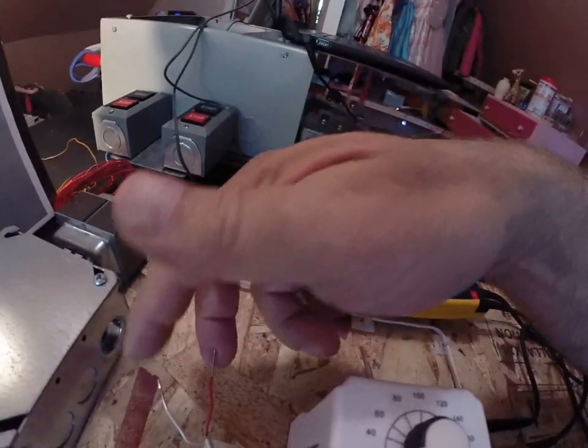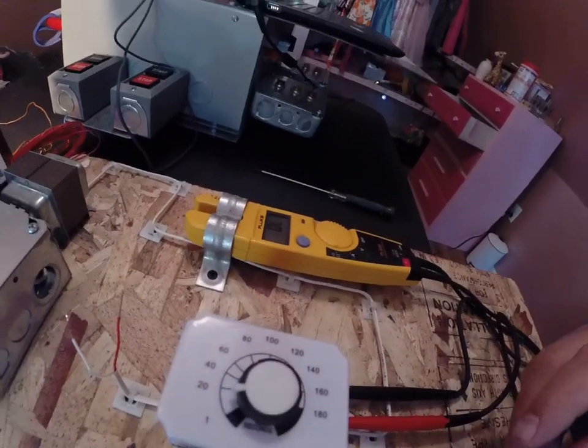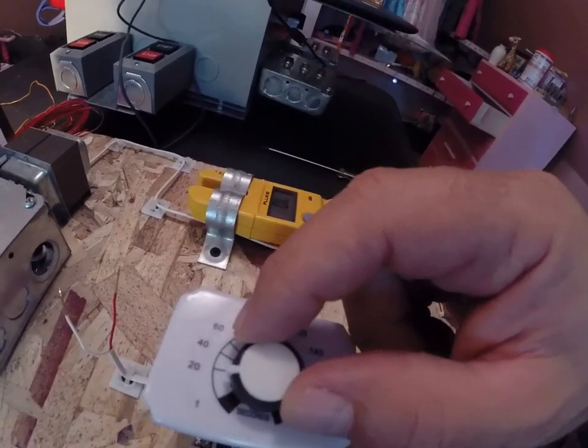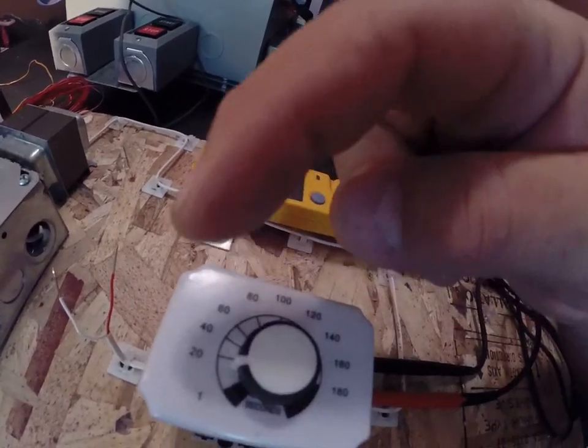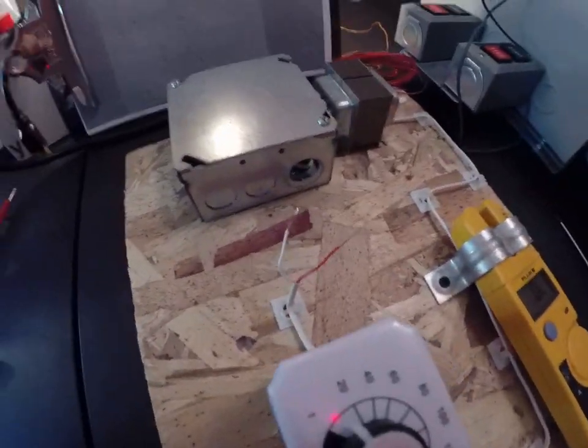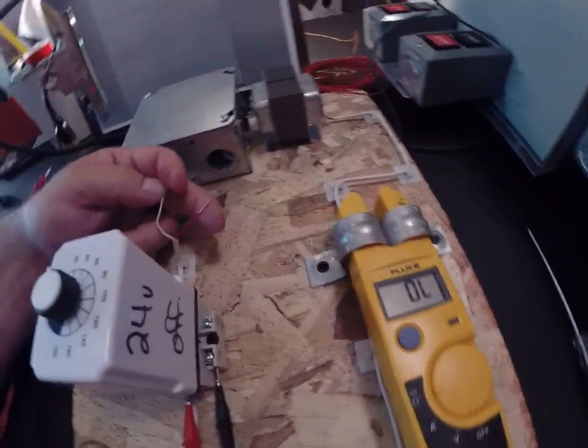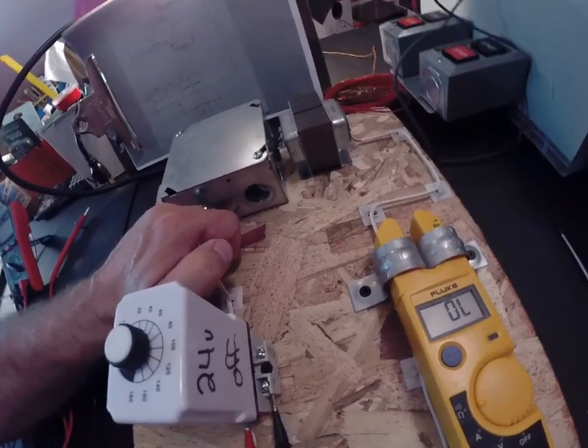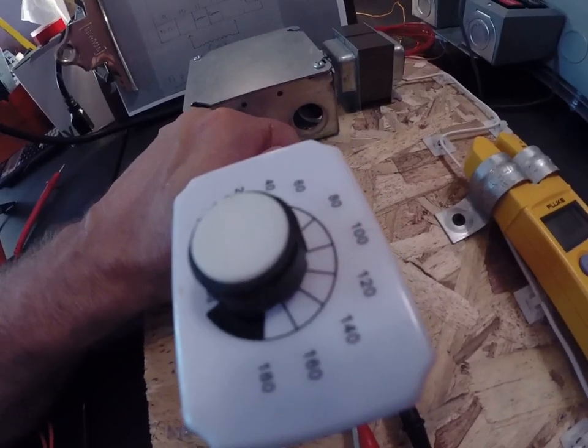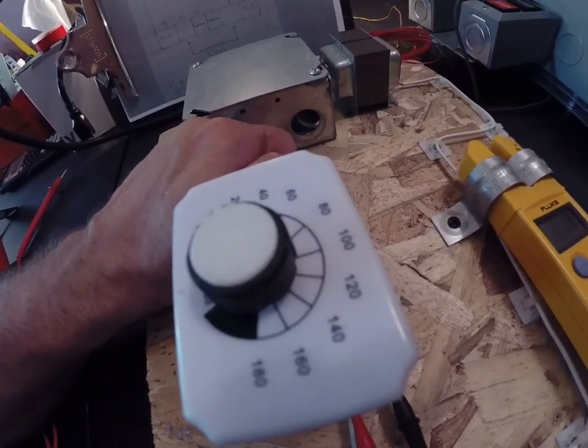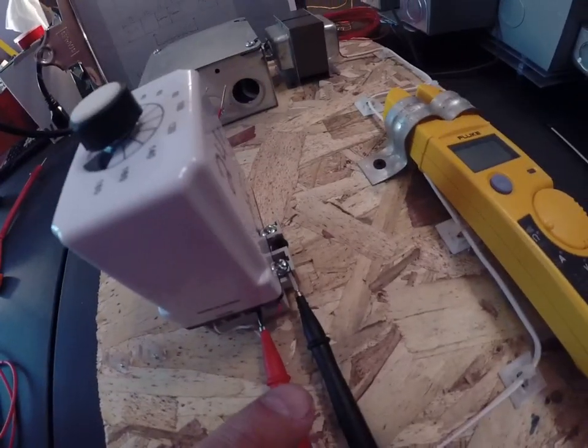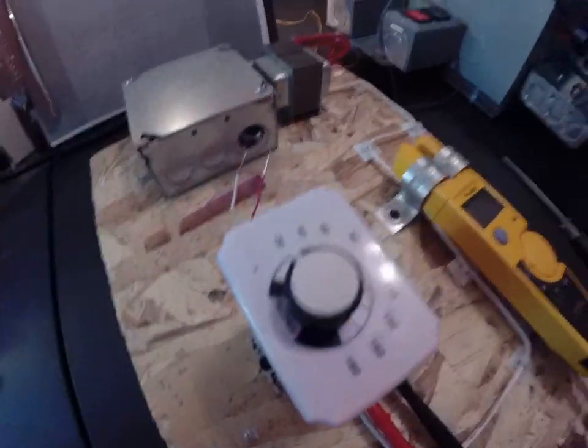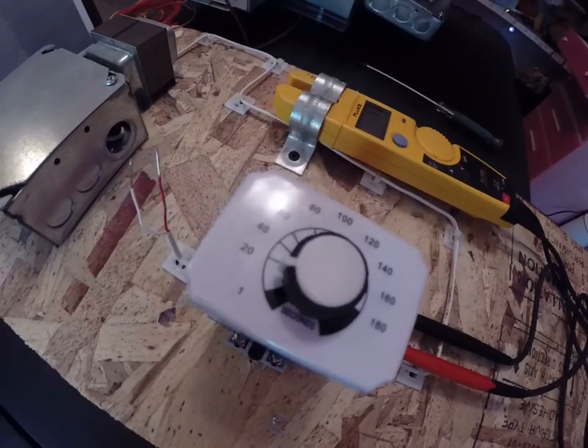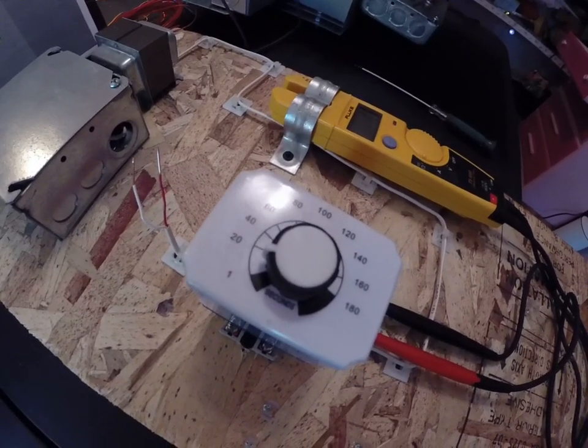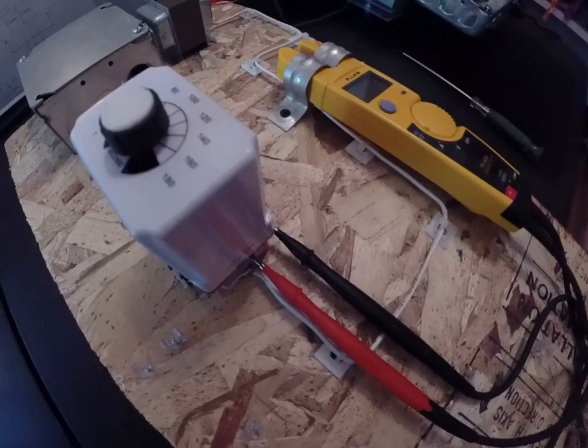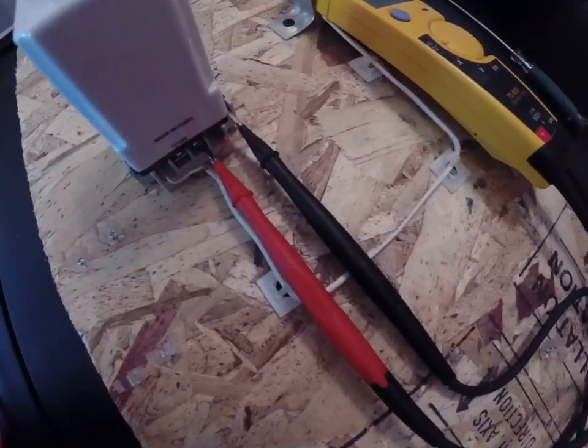So let's pretend that these were already hooked up to a relay, common and normally open. I've got this set for somewhere in the 1 to 20 second range. And what I'm going to do is create the short circuit on this so you can hear my meter. So right now I'm going to create this short circuit. You'll hear the relay click and it's beeping, but as soon as I remove it, it's going to stay beeping for as long as I have the timer set for, somewhere under 20 seconds. And once that times out, it's going to stop beeping and go back to normally open.